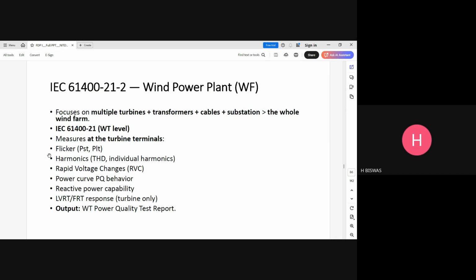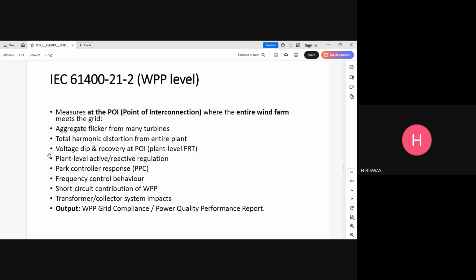And Part 2 is the wind power plant as a whole. So it focuses on multiple turbines plus transformer plus cables plus substation, the whole wind farm. And this Part 21 is wind turbine level. So of course, as we have seen, at the end of the day, we get the wind turbine power quality test report. Now, Part 21-2 gives, at the point of interconnection where the entire wind farm meets the grid.